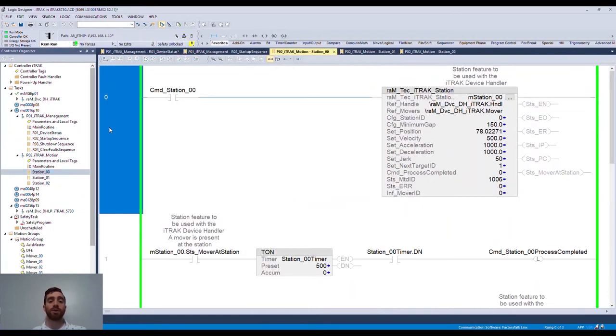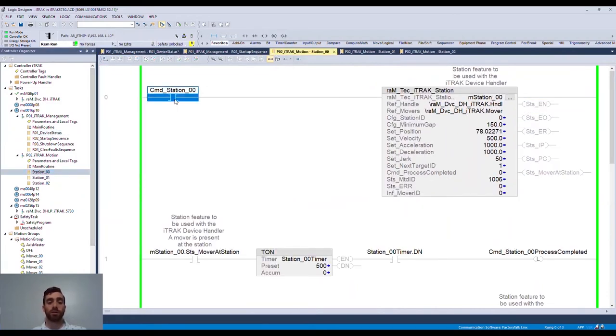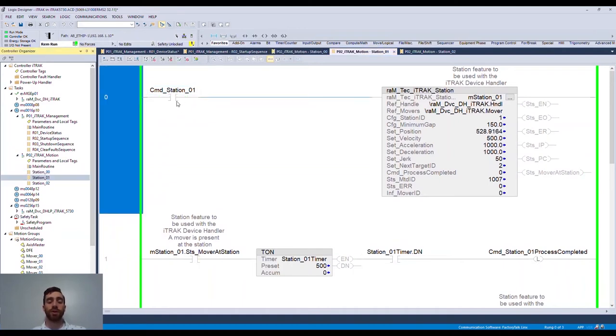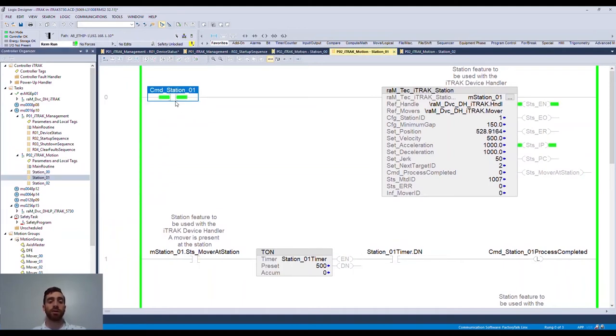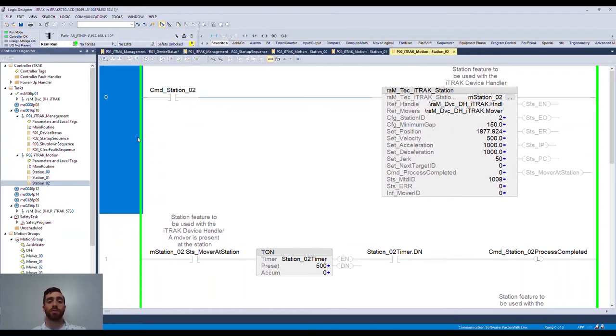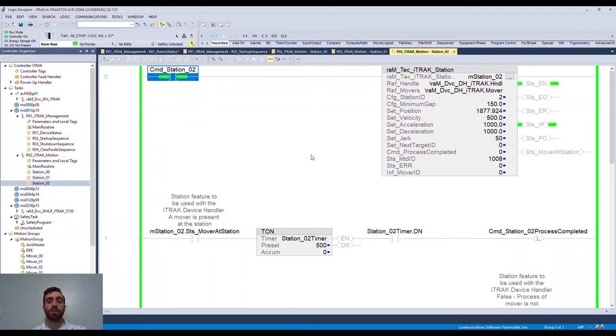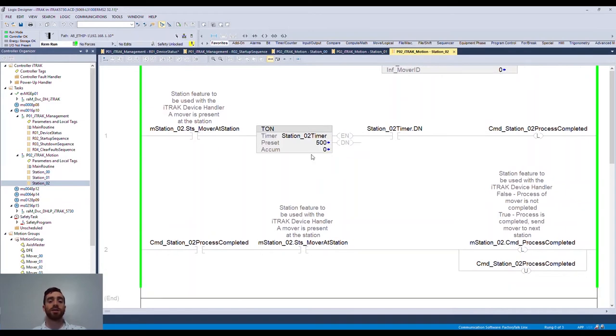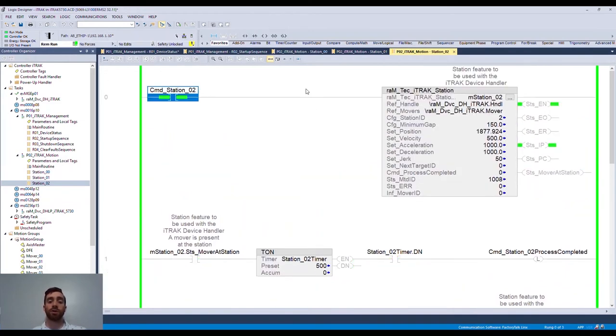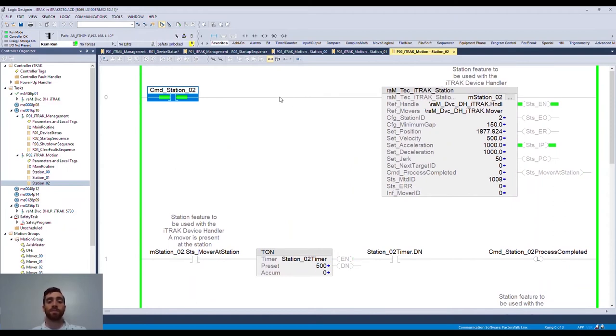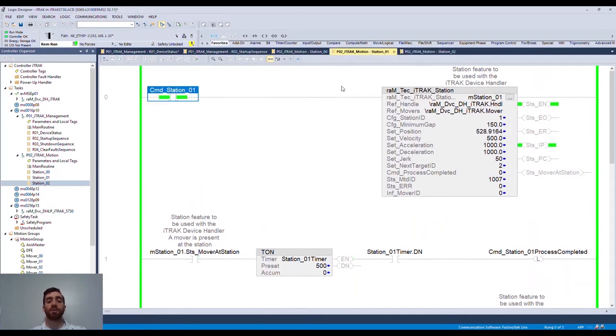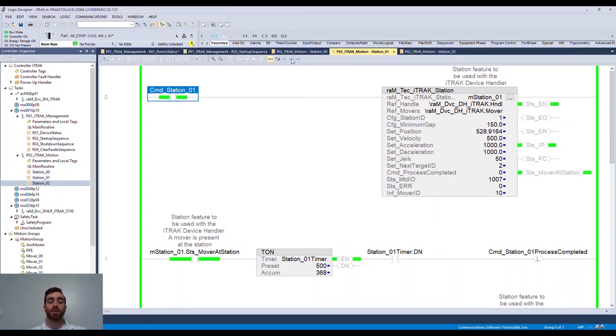With the station logic, all we have to do is enable each of the stations. The station routines have the logic necessary to control the station, including handling station entry as well as completion of the operation. The library adds a timer here to simulate an operation, but it would be easy to change this to whatever your station operation would be. Following our earlier analogy, once your loading is complete for your filling station, you would trigger the process completed bit and the station would send them over to the next station. The same would go for the filling and picking stations.